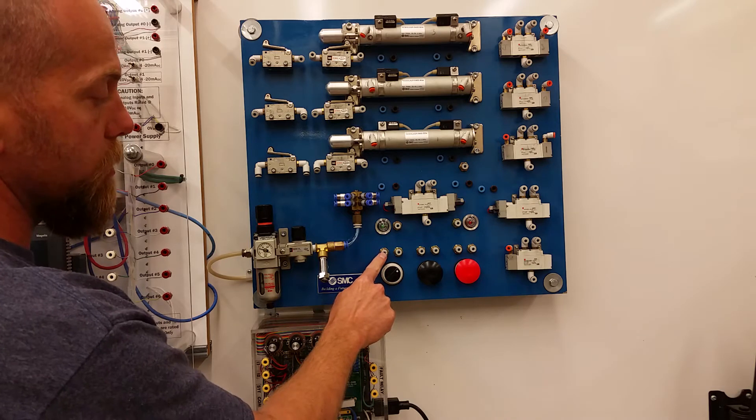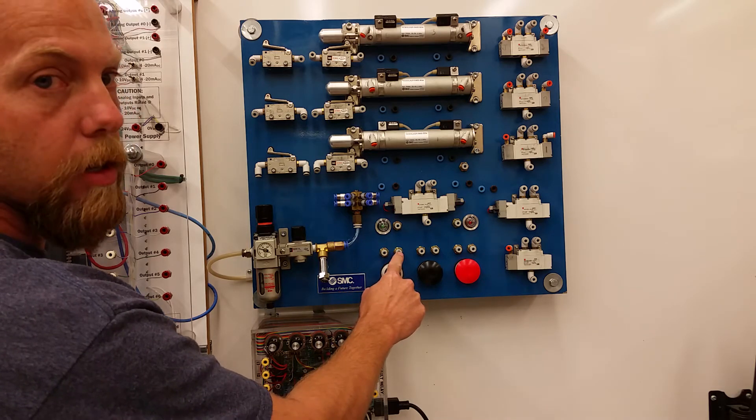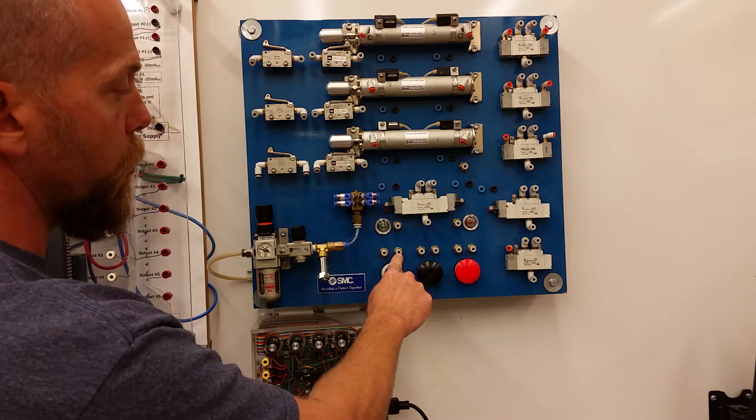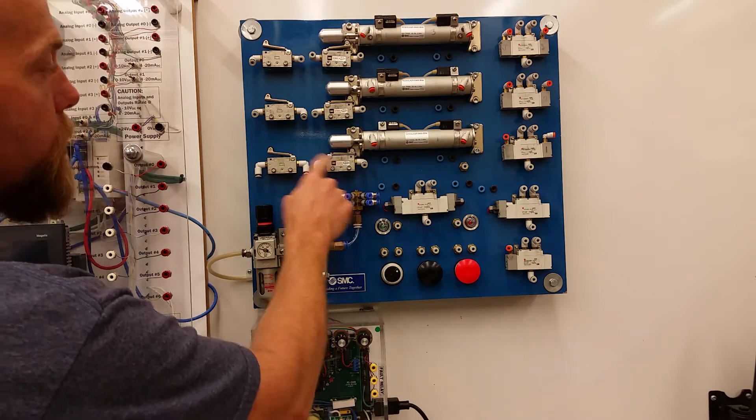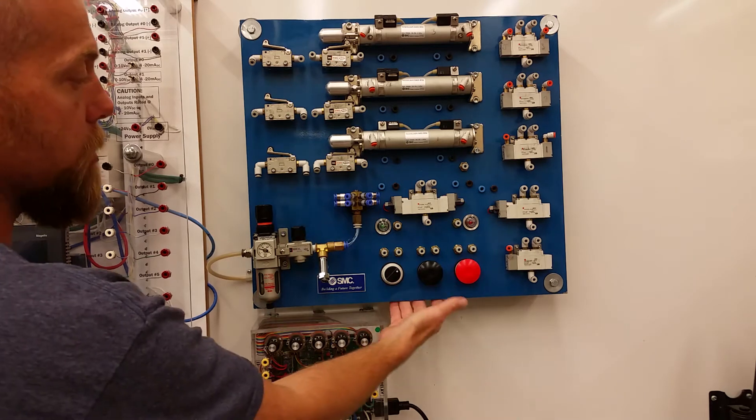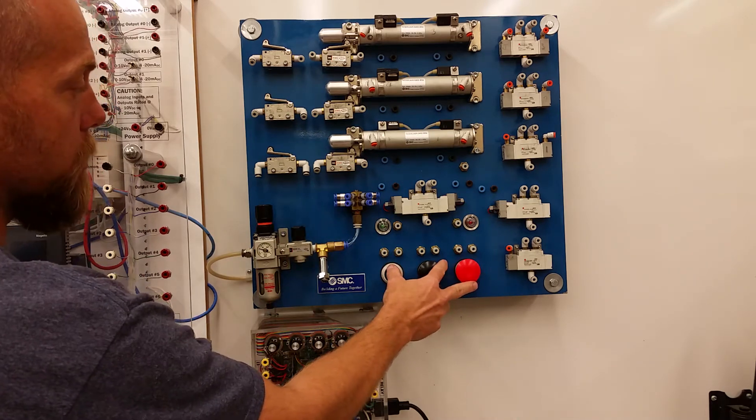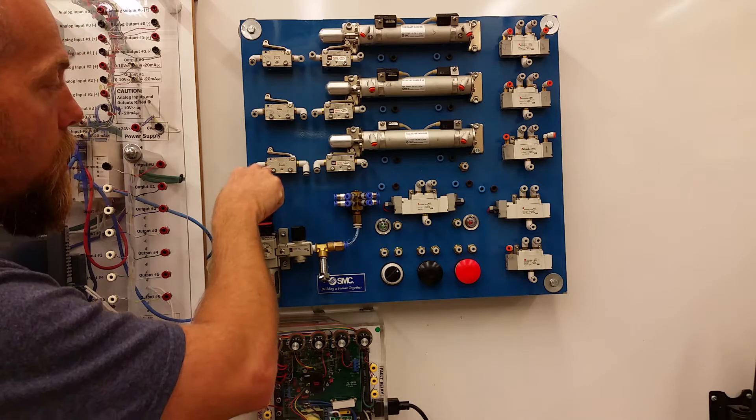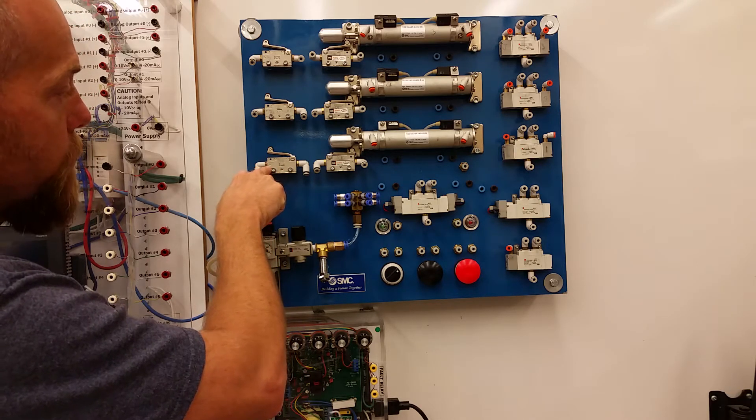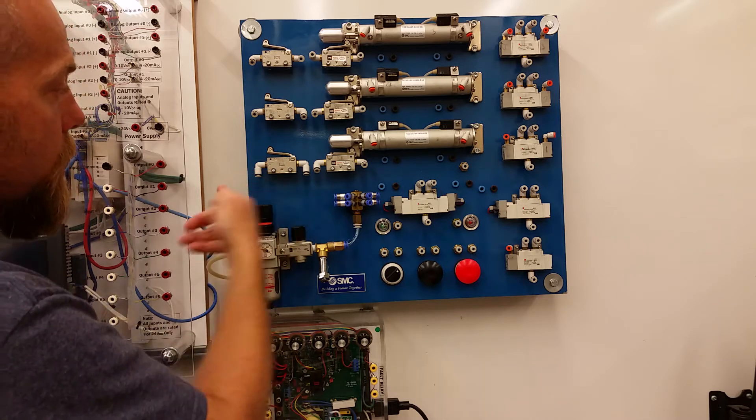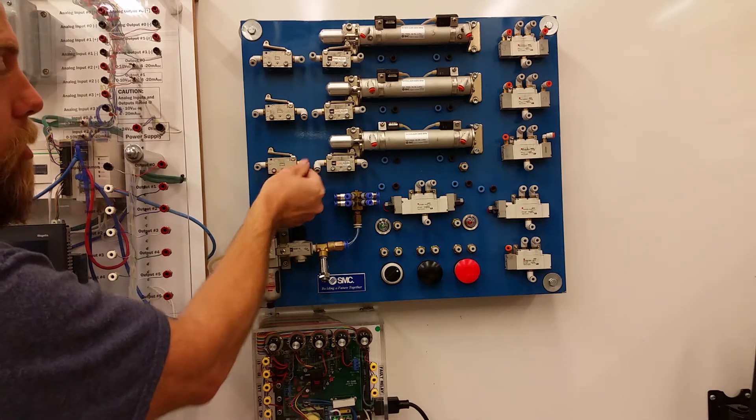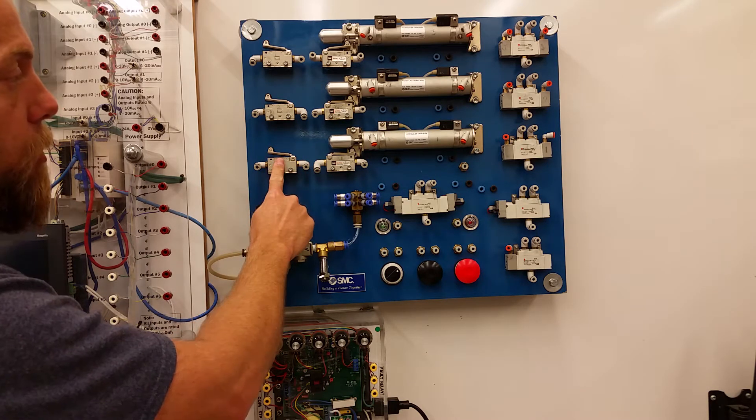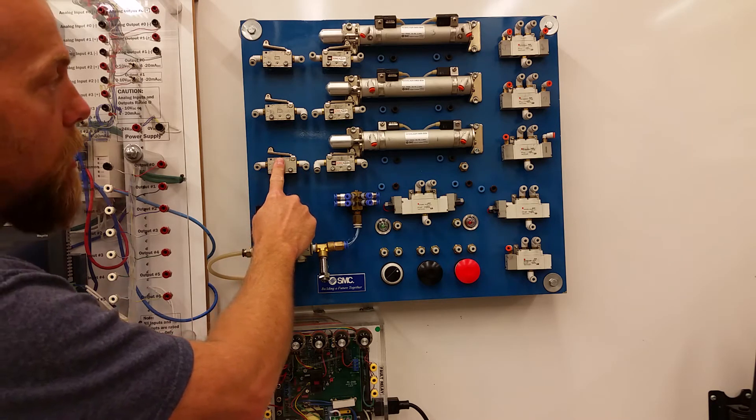These guys have an input on the left-hand side and an output on the right-hand side. This would correspond to port number one. This would correspond to port number two. If you take a closer look at the limit switches, they are the exact same as the 3-2's for the push buttons and the selector switch. But they have a direction of flow. You might not be able to make it out right there. But there is an actual arrow here to denote that the air is coming in. So this would be port number one. This would be port number two. And then integral to the switch is port number three, which is the exhaust.